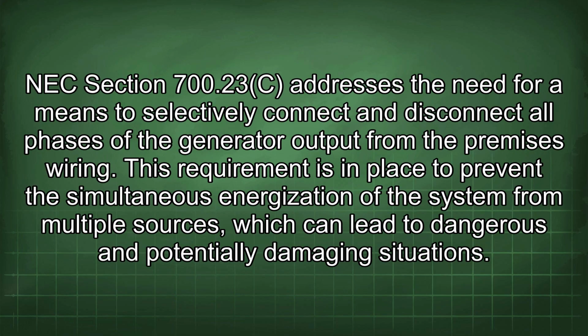700.23(C) addresses the need for a means to selectively connect and disconnect all phases of the generator output from the premises wiring. This requirement is in place to prevent the simultaneous energization of the system from multiple sources, which can lead to dangerous and potentially damaging situations.